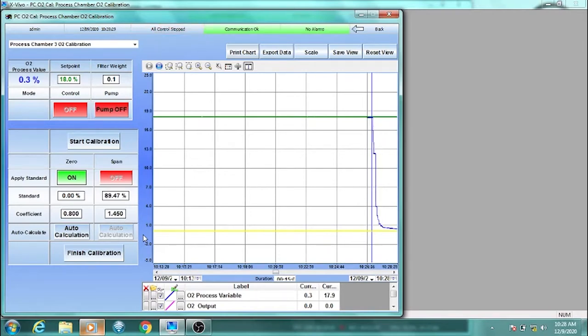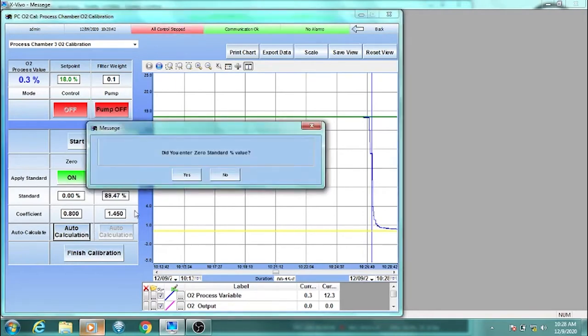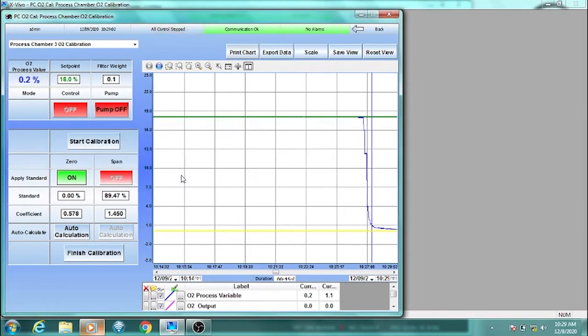If the sensor is not within this range, simply click the Auto Calculation button, and the software will adjust the coefficient for you so that the sensor reads more accurately. The software will ask if you entered the zero standard percent value. This should always be 0.00 because we are using 100% nitrogen and 0% oxygen for zero calibration. Click Yes. Wait a few seconds and make sure the value is adjusted to a reading within plus or minus 0.1 of 0%. Zero calibration can be turned off once finished. Allow a few minutes for the sensor to recover from the exposure to pure nitrogen.